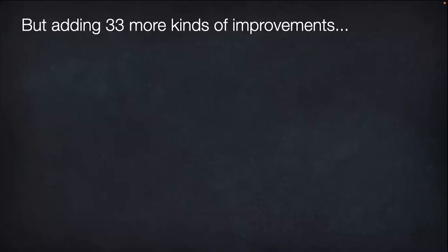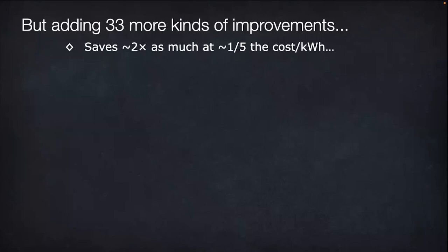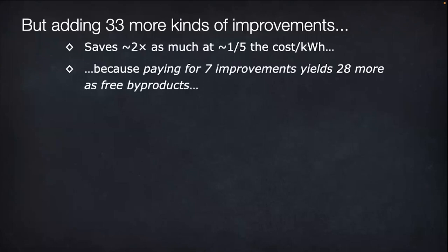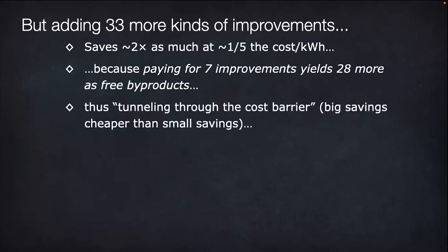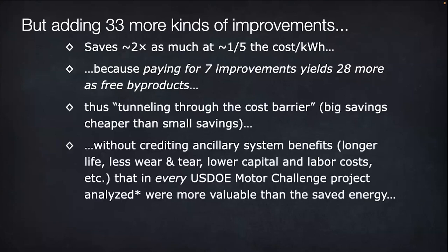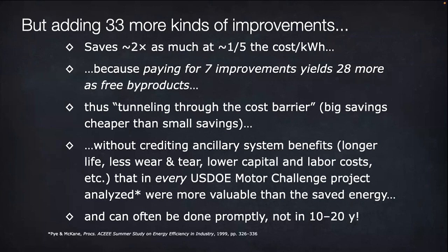So our whole-system approach doubles the savings and cuts the cost per saved kilowatt hour by roughly fivefold, by sequencing not just two but 35 kinds of improvements, of which 28 are free byproducts of the first seven—thus tunneling through the cost barrier and triggering side benefits that, as DOE found, are generally worth more than the energy savings. Moreover, this bigger, cheaper saving needn't wait for routine motor burnout, but can often be profitable to do immediately, increasing the present value.